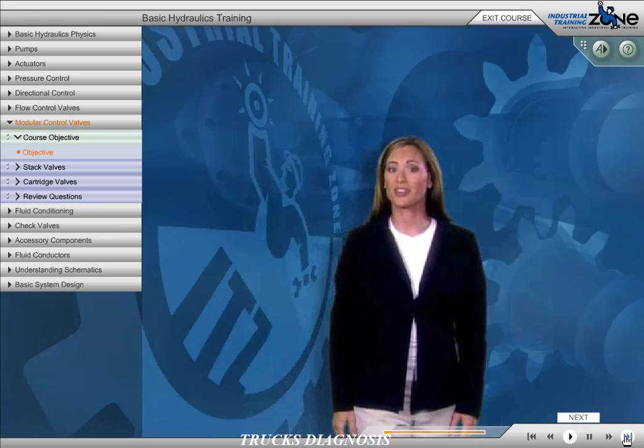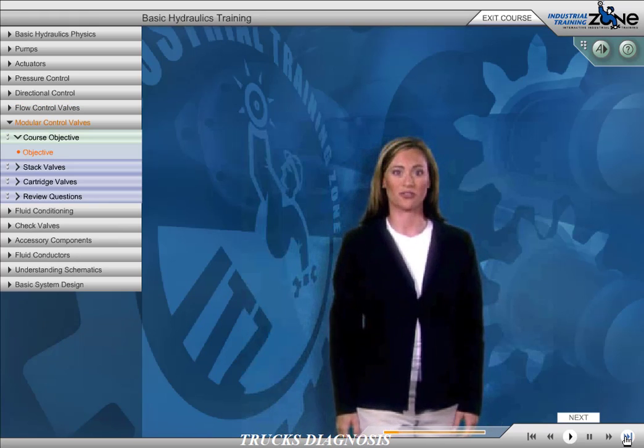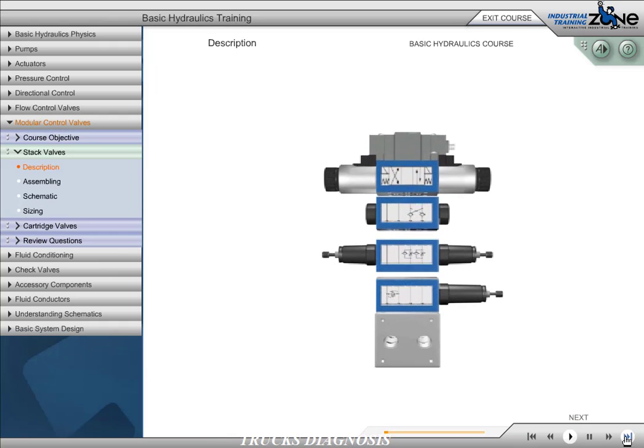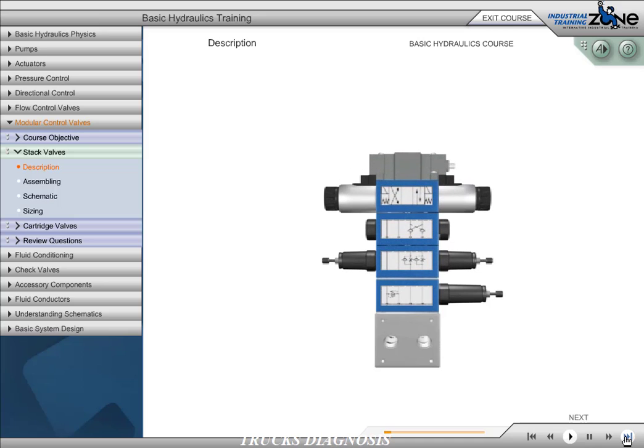Finally, we'll close this section with an overview of modular valves. Stack valves are bolted together in a compact stack, eliminating the need for external plumbing between components. By eliminating the pipes, tubes, and hoses typically used to interconnect the various valve components, the assembly is compact and free of potential leak points. Standard subplate-mounted directional control valves and cartridge-style flow control, pressure control, and check valves are used to create stack valve circuits.